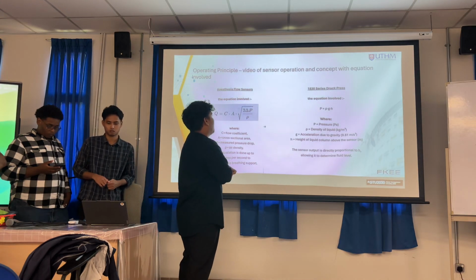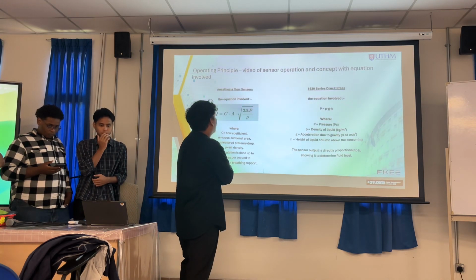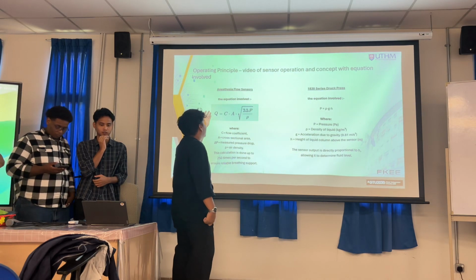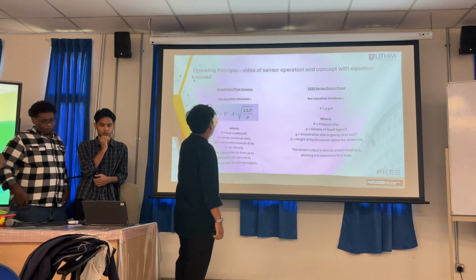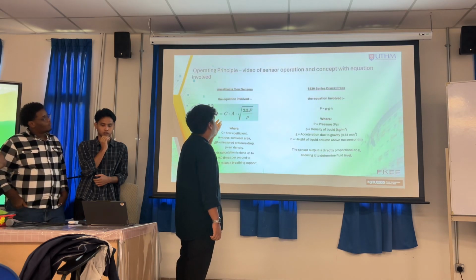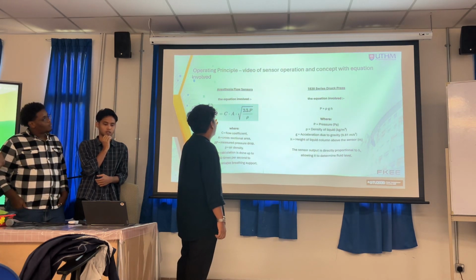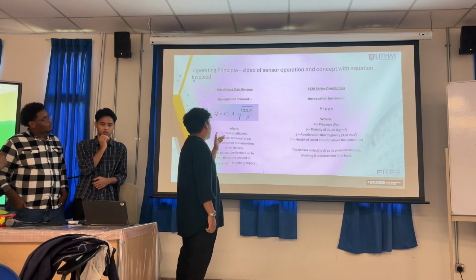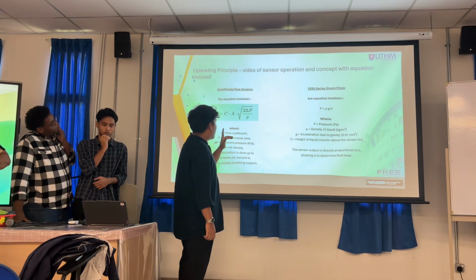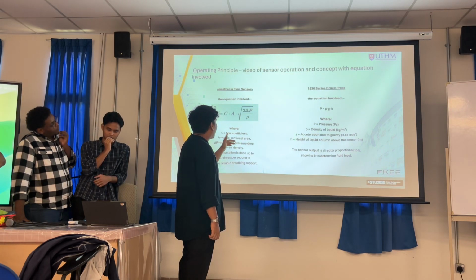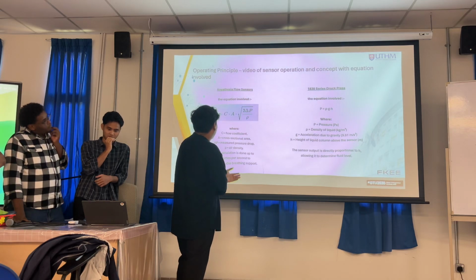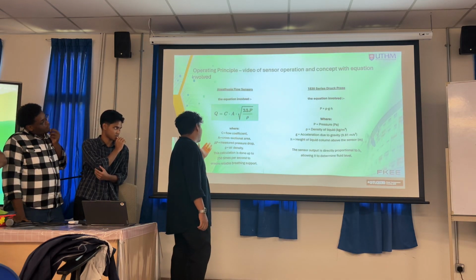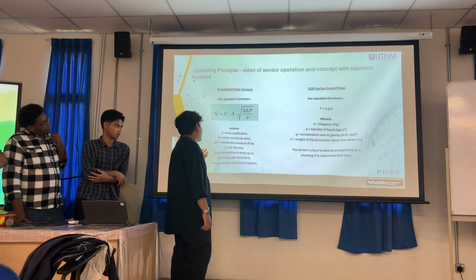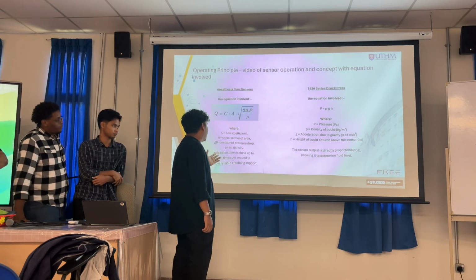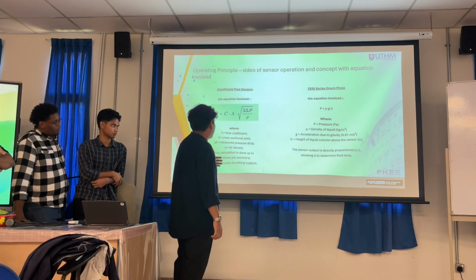So on the video, the equation for anesthesia is Q equals C times A times the square root of 2 delta P divided by air density, where C is the flow coefficient, A is the cross section area, delta P is the measured pressure drop, and P is the air density. This calculation is done up to 250 times per second to ensure reliable breathing support.